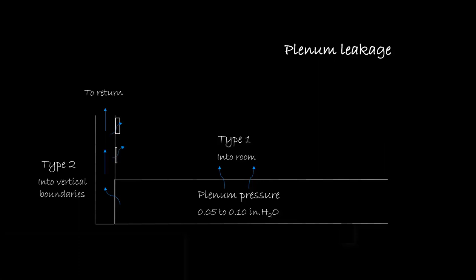Finally, conduits that feed zone thermostats should be sealed in order to prevent inaccurate measurement of the room air temperature.